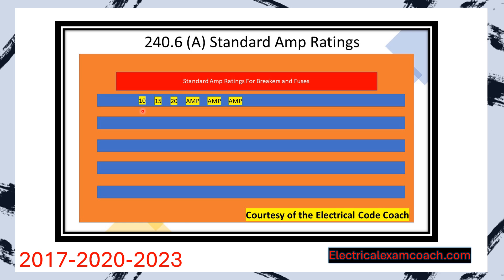When we get to 50, it starts jumping by tens and even larger numbers as we move up in amperage. The reason that this table is so important is it unifies the entire electrical industry. The manufacturers make these size breakers, the stores stock these size breakers, installers purchase these size breakers, and when we are doing our load calculations in the NEC, these are the sizes that we're actually going to use. Table 240.6A — standard ampere ratings for breakers and fuses.